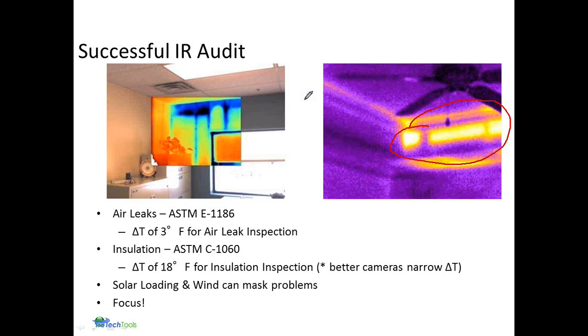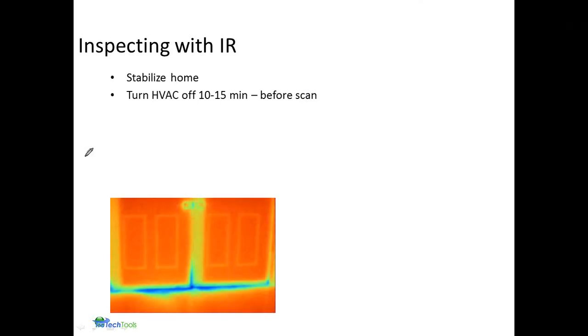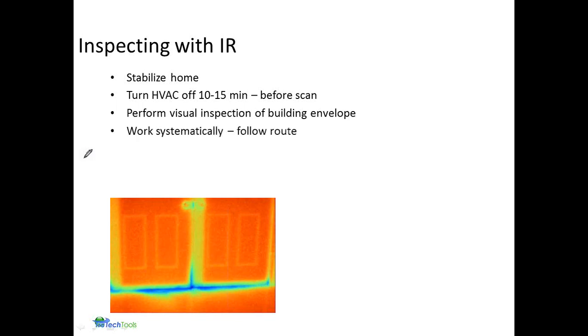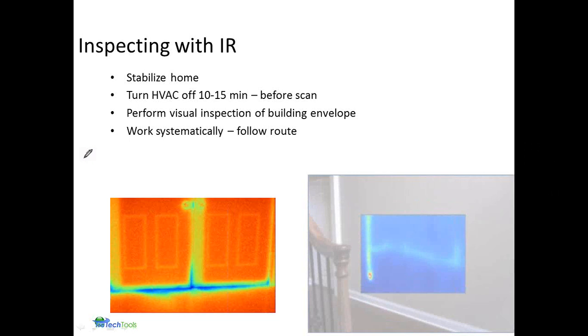Another key point is learning to focus your camera. Extremely important to get good data, not only in presenting it to others, but interpreting it yourself. So inspecting with IR, we would like to have a stable home if possible. It's suggested to turn off the HVAC system before you start your scan to reduce the amount of forced convection that you might encounter. That also helps to stabilize the temperature. You want to perform an effective visual inspection of the envelope and work systematically. Part of the visual inspection is that when you do see an anomaly, you'll remember the fact that you saw something that could cause you some issues when you're trying to do that thermal scan.